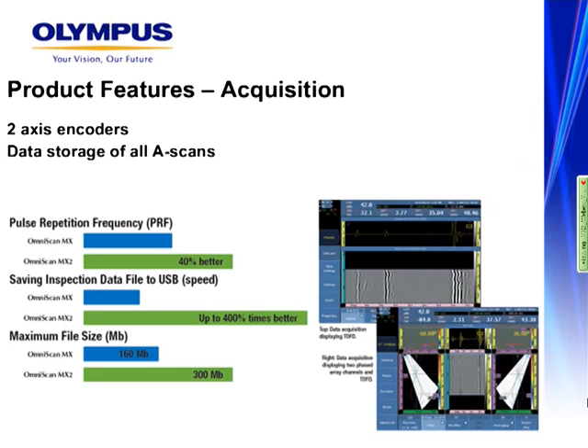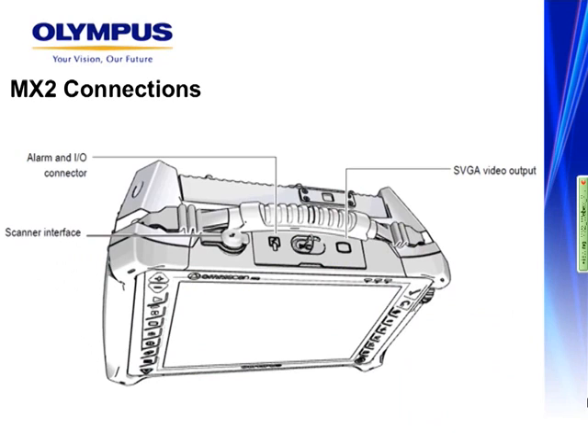A typical example of a two-sided weld inspection with two phased array probes, two sector scans, and one TOFD channel, with all groups acquired simultaneously, is now approximately 100 millimeters per second. Again, about a 40% improvement over previous versions.